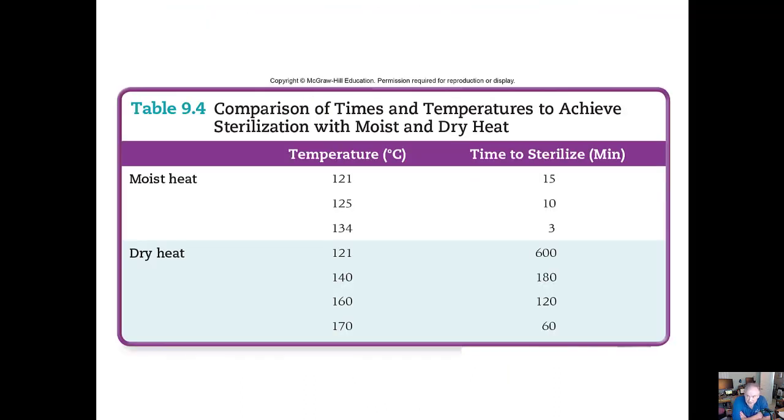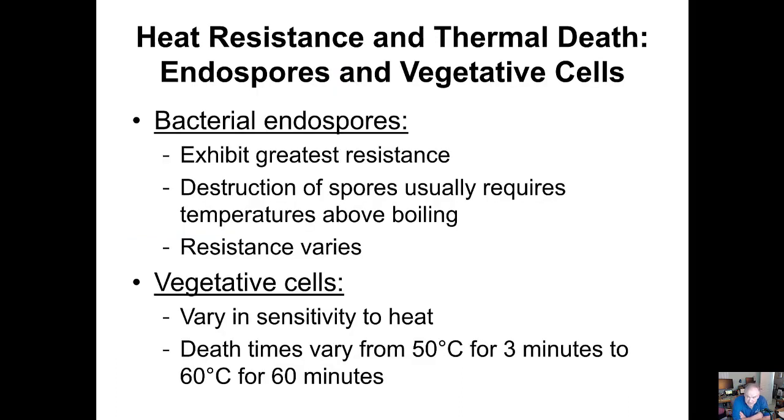Moist heat, the magic number is 121 degrees centigrade for 15 minutes. You can go to a higher temperature, 125 for 10. But the industry kind of standardizes on the 15 minutes at 121. It's kind of strange that that's the bare minimum to get rid of spores, and so that's what we're doing there. And as I say, we usually put a fudge factor in there, like 125 degrees for 15 minutes, and it's just guaranteeing. Or you can go for 20 minutes at 121, something like that. It's whatever the place that you work at with their SOPs have determined that they want to use.